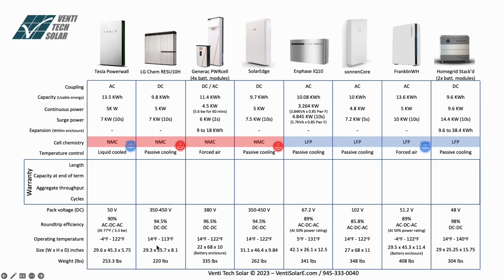So again, liquid cooling will allow them to work in more extreme environments. Passive cool here, they have to raise the low end and lower the high end of the operating temperature. So that makes sense. It's passive cooling, still NMC. I think these numbers are acceptable. I would want to make the high end a little lower and the low end a little higher, but it's still acceptable. In the Generac, again using NMC, they are matching 122 degrees, matching it to Tesla, which is a stretch. And the 14 degrees, they have to raise that temperature compared to Tesla, which is okay. I would like to see this 122 lowered as an operating temperature for that one.